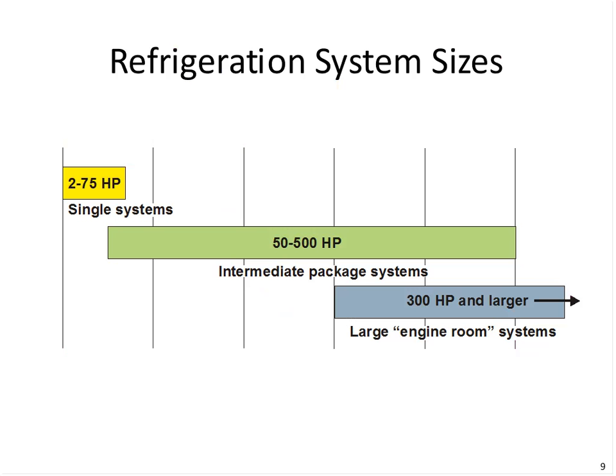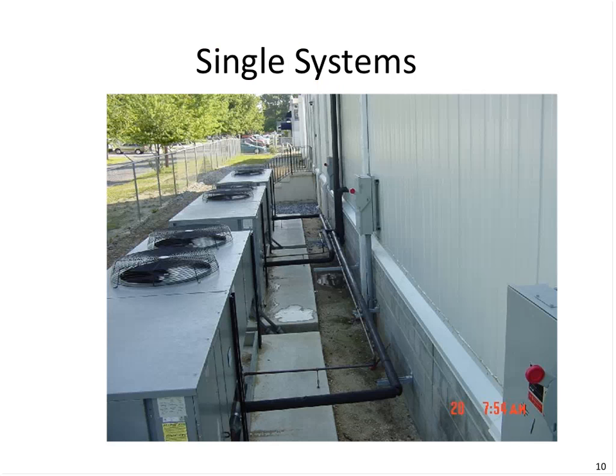Okay, so refrigeration systems typically fall into one of these categories, suggesting that between 2 and 75 horsepower quite often is catalog type equipment, sometimes just known as single systems, and we have several single systems, but this implies one compressor, one condenser, and one evaporator. I'm going to switch to the next slide for a second. Here we go. Single systems. Typically, the refrigerated equipment inside the refrigerated space here, but here we've got a piece of catalog equipment. Inside here is the compressor. Here's the condenser, refrigerant lines, and notice we've got 3 separate single systems here.